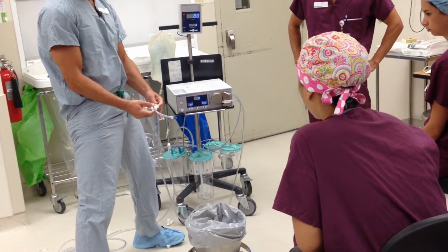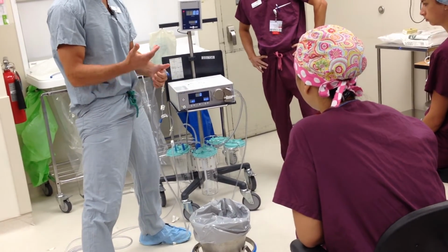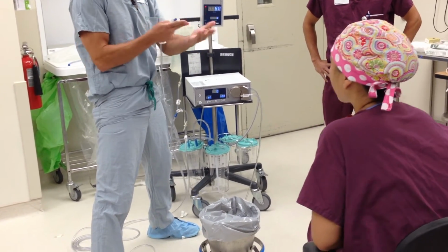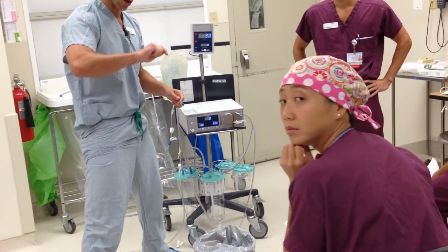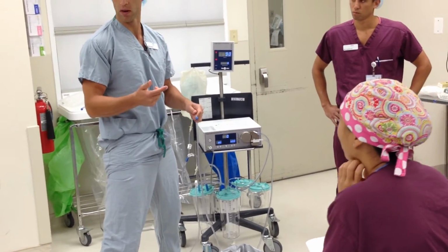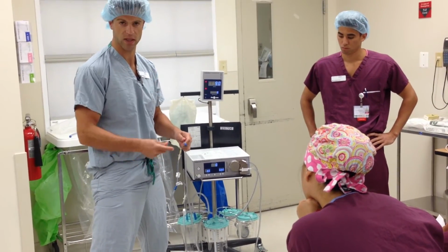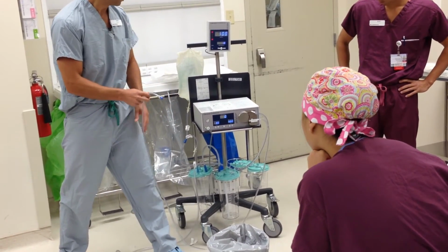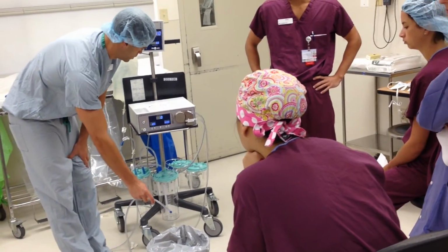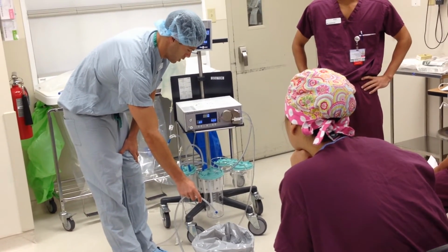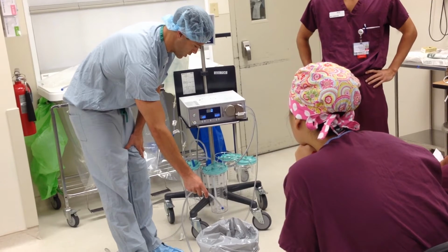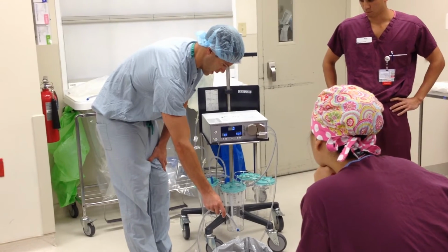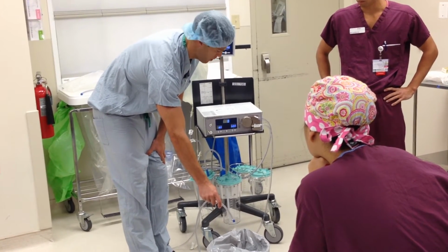So you've got everything open. Basically, what you're going to have in order to do the priming is the scope in the sheath, like everything set up like you would do in the case. Close the outflow, because the outflow isn't going to be a part of this priming or equipment detection. Leave the inflow open. So you start the pump. And so I would just try to get as many of the bubbles out as possible. It's not going to be perfect, but just the majority of them.